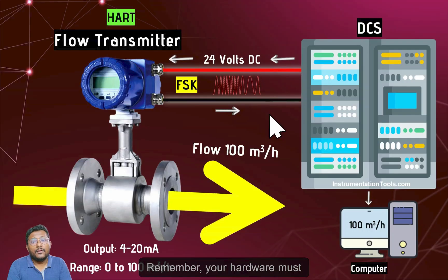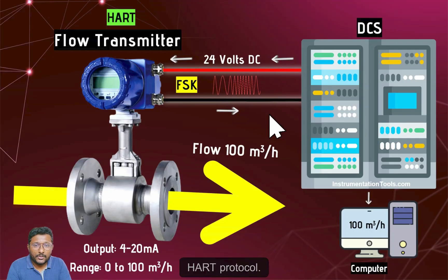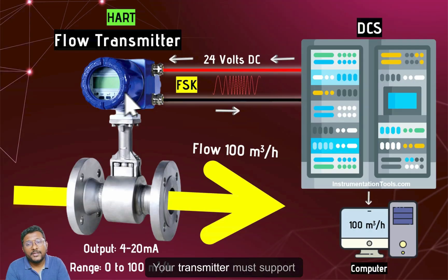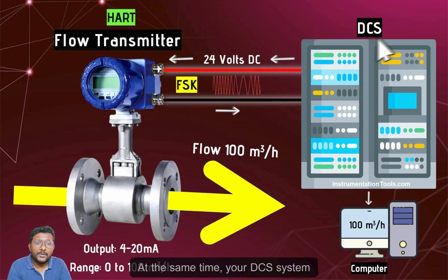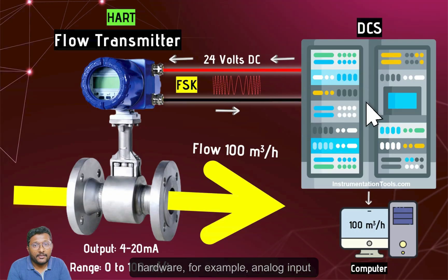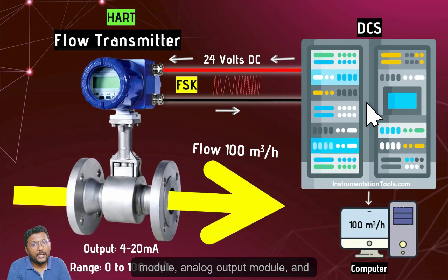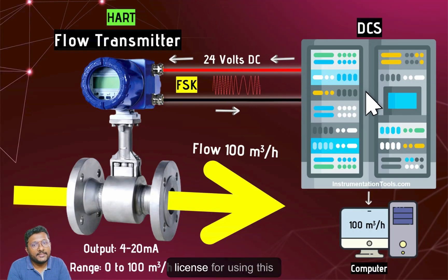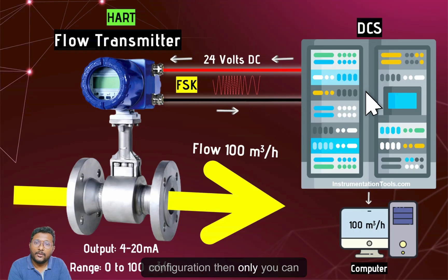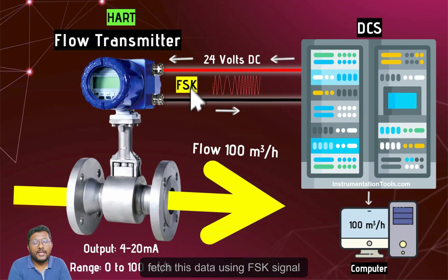Remember: your hardware must support HART protocol. Your transmitter must support HART signal transmission, and at the same time your DCS system hardware — for example the analog input module and analog output module — must also support HART protocol signal. At the same time you must have a software license for using this HART signal configuration. Then only you can fetch this data using the FSK signal.